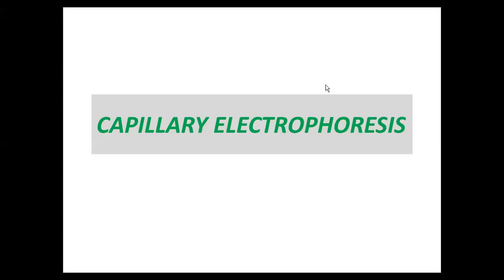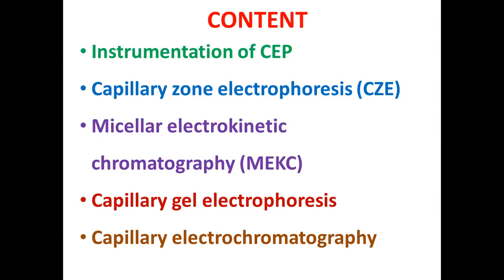Today we continue our discussion on capillary electrophoresis, which is an extended discussion on electrophoresis. Electrophoretic techniques are classified in several ways, and among them, capillary electrophoresis is one of the important techniques widely employed for both qualitative and quantitative analysis. We will concentrate on the instrumentation of capillary electrophoresis. Capillary zone electrophoresis can separate cations and anions, but the principle is not suitable for separation of neutrals.